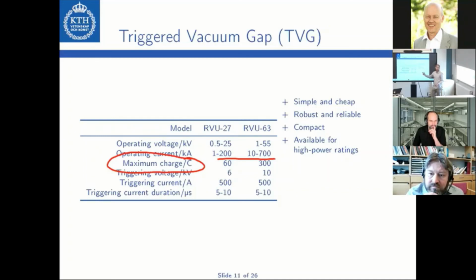But there's a clear limitation. However, if you consider that this is 300 coulombs, if one does the math, this will amount to a time which is substantially higher than an IGBT could conduct breaker current for. So for instance, with the IGBT, you would need to connect units in parallel at some point. Here you can still operate it. One also has to say that since it's such a simple device, and not made for the DC circuit breaker, a device optimized for the DC circuit breaker could conduct even longer, or higher currents—it's part of the optimization.